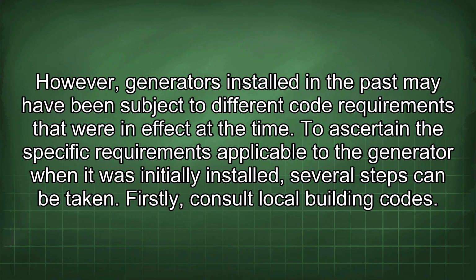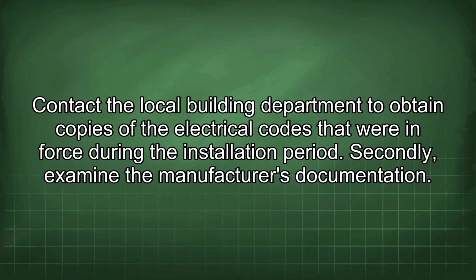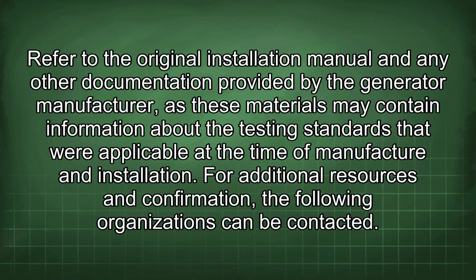Firstly, consult local building codes. Contact the local building department to obtain copies of the electrical codes that were in force during the installation period. Secondly, examine the manufacturer's documentation. Refer to the original installation manual and any other documentation provided by the generator manufacturer, as these materials may contain information about the testing standards that were applicable at the time of manufacture and installation.